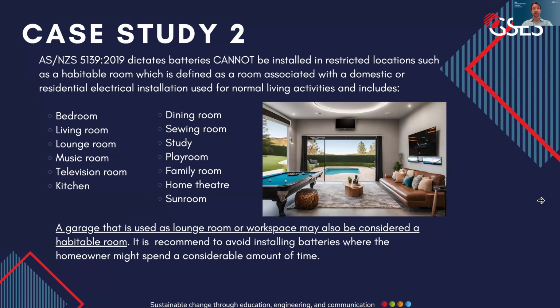It is important for the installer to understand the intent or spirit of the standard, which is ultimately to protect personnel and property. The example that we're showing here is a garage, which is deemed not to be a habitable room, which has been converted into an entertainment space. Making this change means that this is now considered a habitable room, and a BESS can no longer be installed here. We appreciate that there might be some gray areas to this, but again, the intent or spirit of the standard must be understood, and a reasonable and rational approach should be taken by the installer.